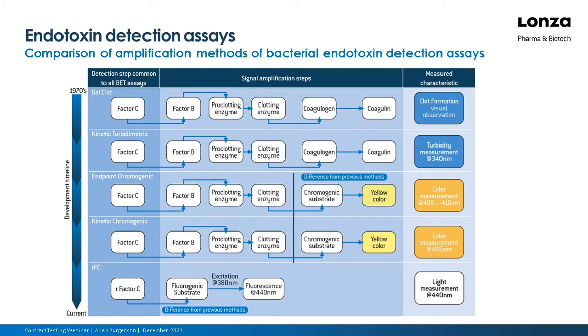But now coming to recombinant factor C, all those other steps you see in the middle column are all amplification steps. But with a factor C assay, you don't need any signal amplification steps because you're generating light, and light is much easier to measure. So the factor C, when it contacts endotoxin, will cleave the fluorogenic substrate, and when you excite it at 380 nanometers, you will get fluorescence at 440 nanometers, and so you're measuring light output, which is proportional to the amount of endotoxin in the product.